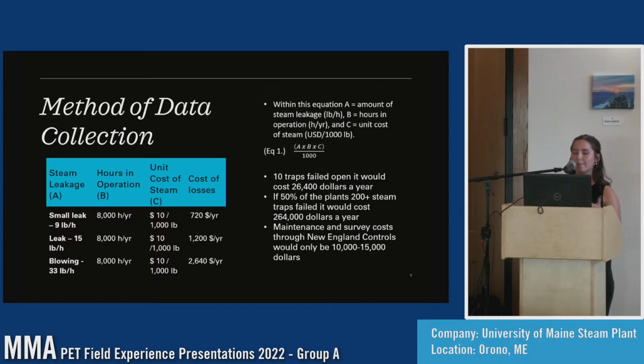So if hypothetically we have 10 steam traps that have completely failed, we will lose $26,400 per year. And if, like the quote said, 50% of the plant's 200 plus steam traps fail, it would cost up to $264,000 a year. So we have a quote from New England Controls that would only be $10,000 to $15,000 to do all of the maintenance. The survey is free initially, and so it would be really cost effective to do this for our steam plant.